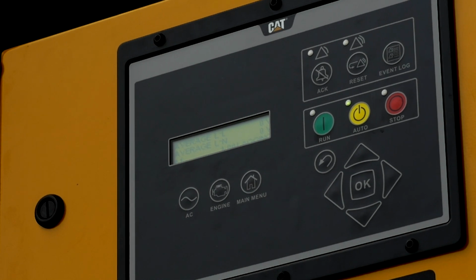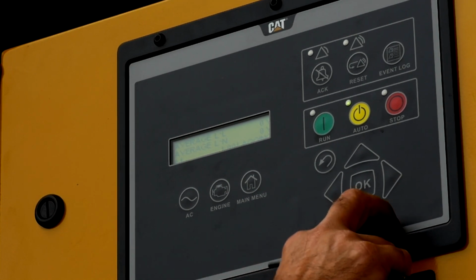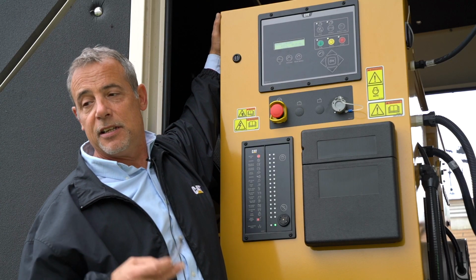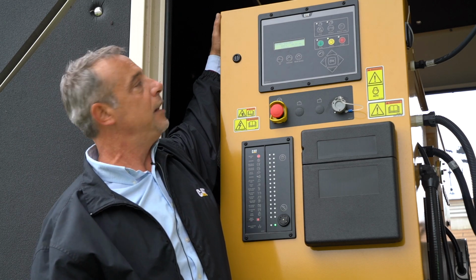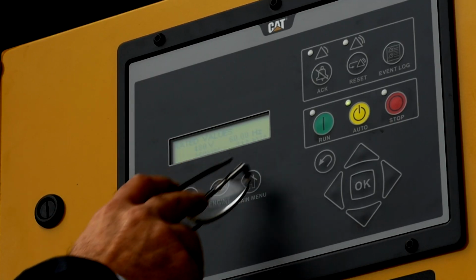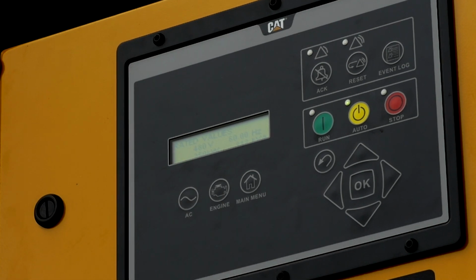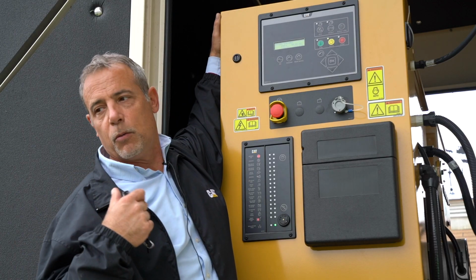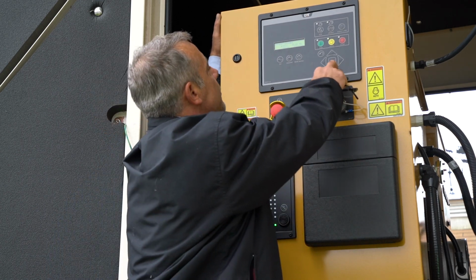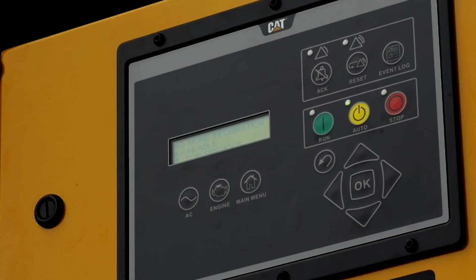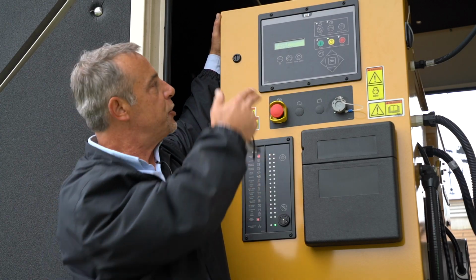The next page will give your average line voltage, line to line, line to neutral, and your power factor, whether it's leading or lagging. The last page tells you what the generator voltage is rated at and what the generator kW is rated at. So basically 480, 60 hertz, 250 kW, and 313 kVA. So if you didn't know what the generator was, you could scroll down to the bottom. When you get down to the last page, it's just going to show you an arrow pointing up, no more. And then you would just arrow back up.